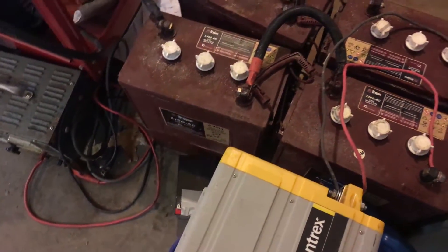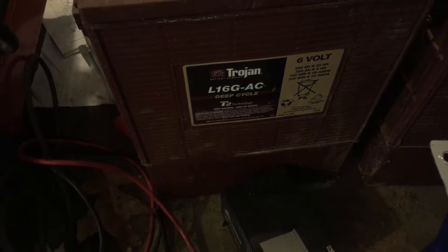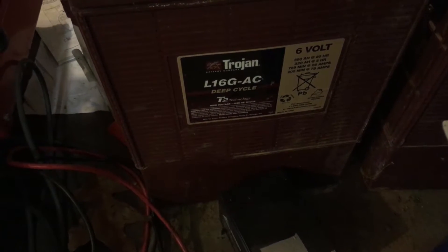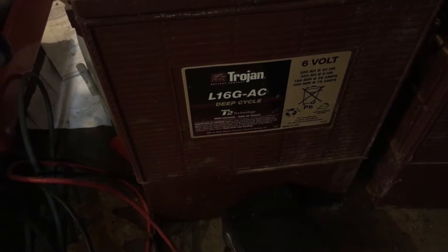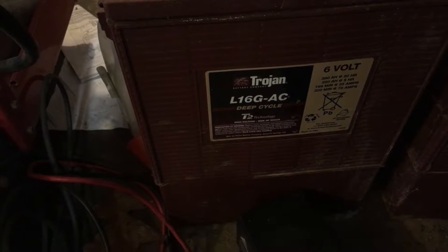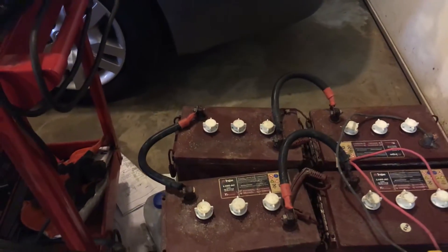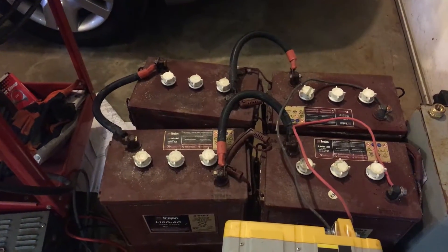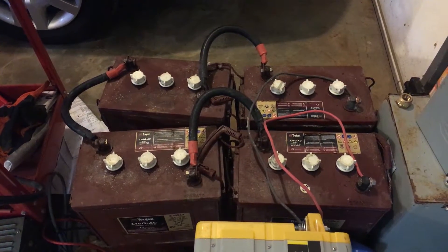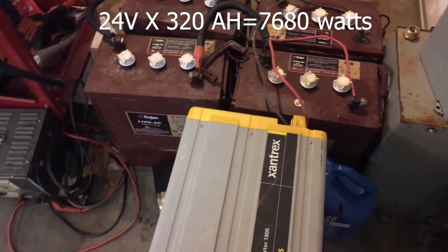As a reference, in one of my previous videos I'm running four Trojan L16G-AC deep cycle batteries, which have an amp hour rating of 320 amp hours at five hours — that's the number we'll use in the calculation. They are wired in series, giving me 24 volts: six volts per battery times four is 24, and the inverter is a 24 volt inverter.